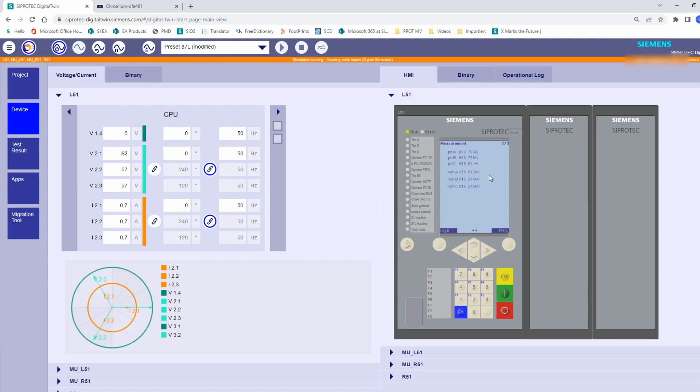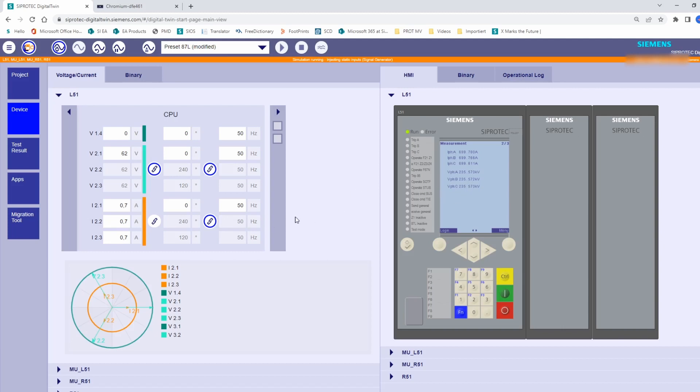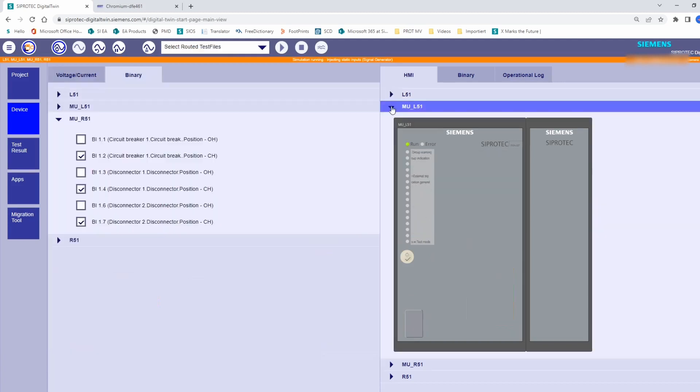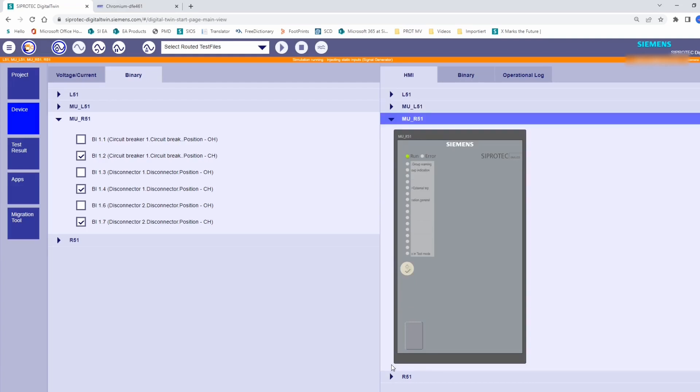On the other side, the trip is released by the protection device, but the circuit breaker is connected to the merging unit. This means, we need to send a trip command from the relay to the merging unit. For that, we also use these GOOSE messages. Here I have also prepared some LEDs in the merging units to show the external trip indication being received and the corresponding operation general originated in the merging unit.